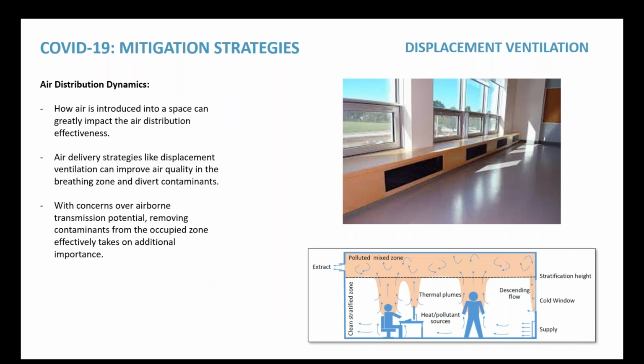One of the other systems that I like to discuss, we don't see a lot on existing building retrofits because it's a little bit difficult to do, but on some of our new designs, is displacement ventilation systems. Displacement ventilation differs from what I would call traditional overhead ventilation in a few different ways, in that overhead ventilation is really what you would call a well-mixed model. You're mixing a lot of the air in the space to provide thermal comfort to the occupants. While that's good for thermal comfort, it's not necessarily great for IAQ because you may have contaminants in the air that are being mixed, and you're not getting rid of them quickly enough.